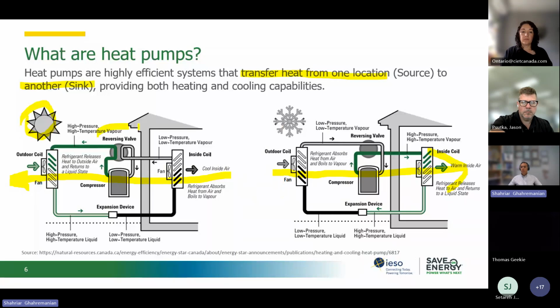And thanks to this reversing valve, which is one extra component within heat pumps that air conditioning systems don't have, the outdoor unit and indoor unit can switch and become a condenser and evaporator based on the season or the operation that we want. So the good reasons to use a heat pump are that they are efficient, and that we can use them both for heating and cooling purposes. These are the first reasons that we need to consider heat pumps.